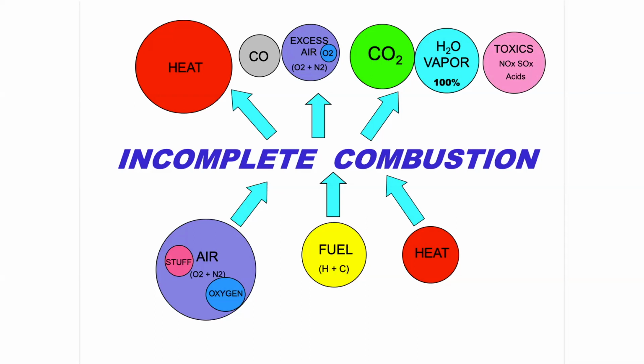Various toxics can be present, and those toxics can actually be formed by stuff that's in the air or the fuel. If there's sulfur in the fuel, for example, if this is, say, an oil system using a higher sulfur oil fuel with hydrogen sulfide, you can get sulfur dioxide gas. The nitrogen in the air can also form with the oxygen, and in many cases, you'll see nitric oxide, NO or NO2. It's not something we typically test for unless you're doing some emissions type work. And you can also get soot, and the soot traces back. It's got the same color as the fuel because soot is basically carbon particles that have formed together. So it's just raw carbon.